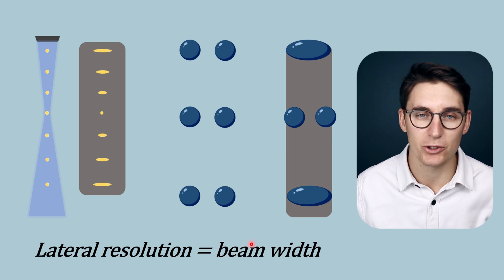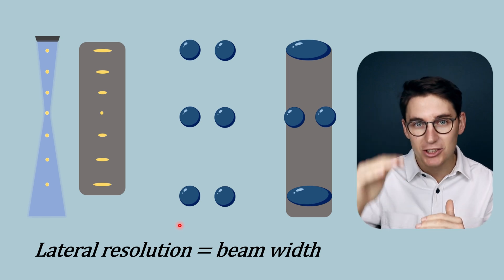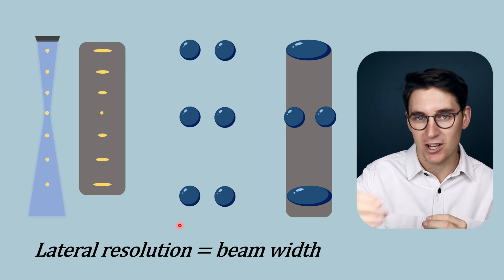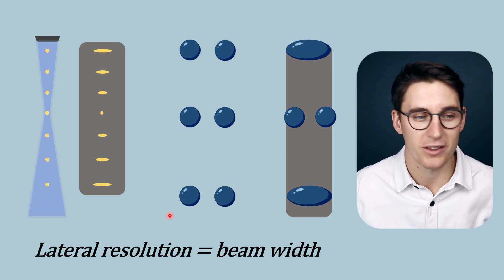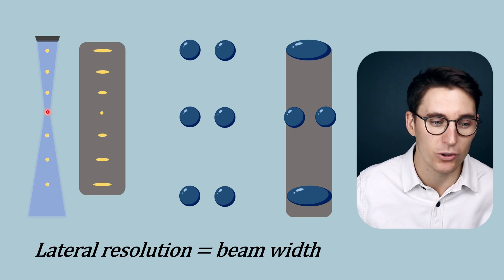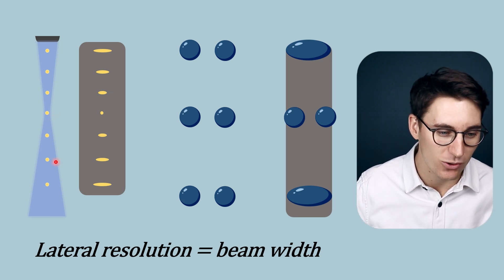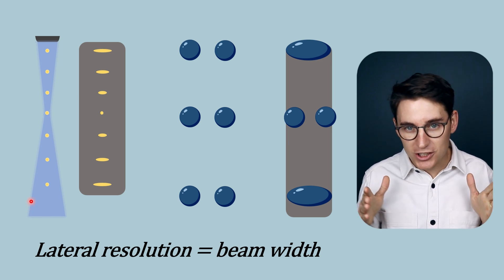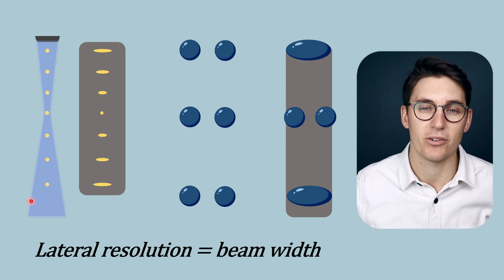Lateral resolution is a function of beam width. Unlike axial resolution — where the frequency and spatial pulse length don't change as the wave heads into tissue — what does change with depth is our beam width. We start with a wide beam width that narrows toward our focal zone at the end of the near field, then diverges again in the far field. So lateral resolution improves as we head toward the focal zone, then gets worse heading into the far zone. Lateral resolution changes with depth.